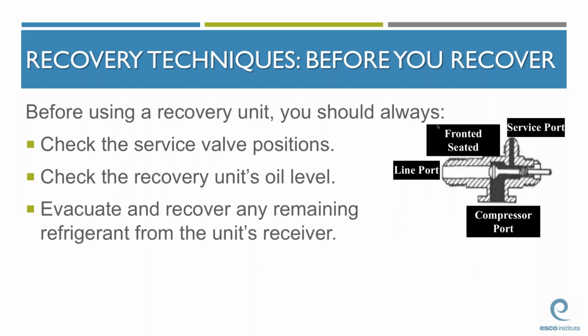Make certain that your students know how to properly prepare and set a system up for a refrigerant recovery process. Before recovery, always check the service valve positions, check the recovery unit's oil level, evacuate and recover any remaining refrigerant from the unit's receiver. Now, I just want to bring up one term.